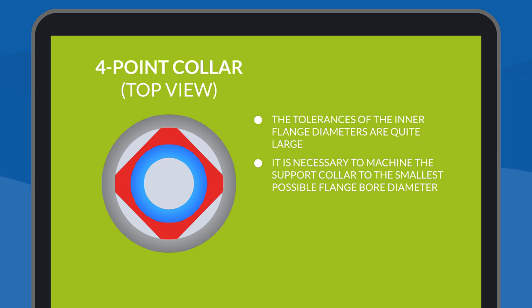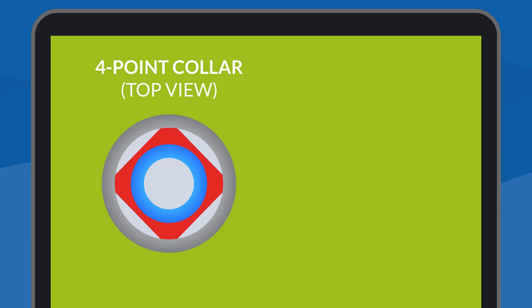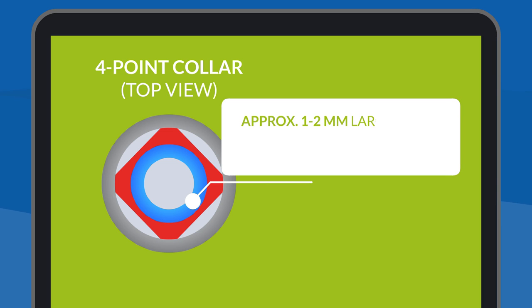However, if the flange bore is now below the upper tolerance, a gap between the support collar and the flange is the result. Thereby, we recommend manufacturing a support collar which is approximately one to two millimeters larger than the maximum specified inner flange diameter.